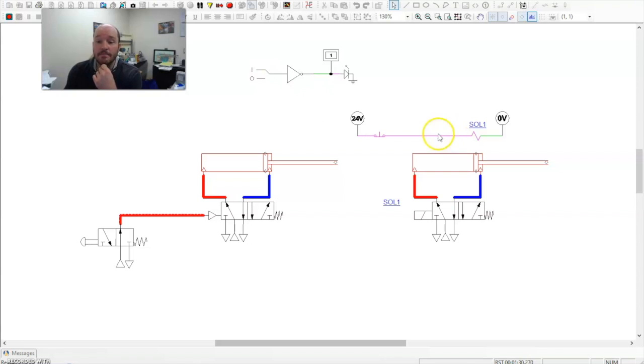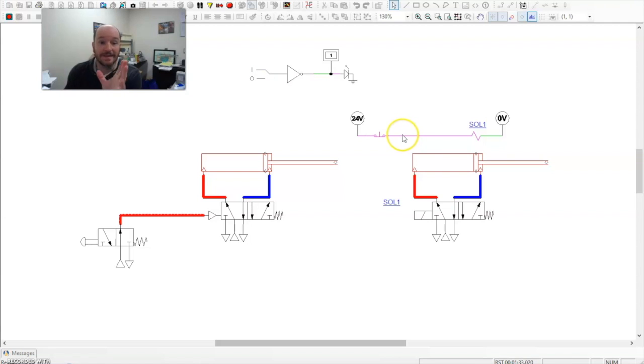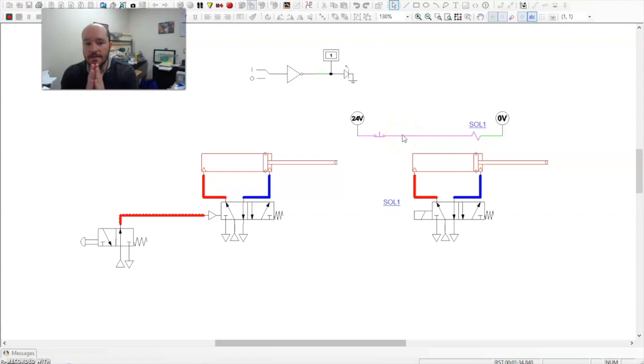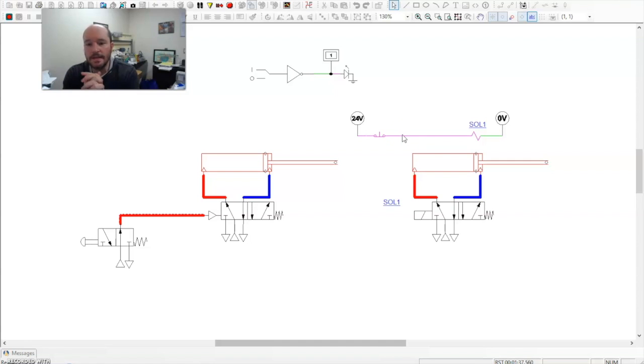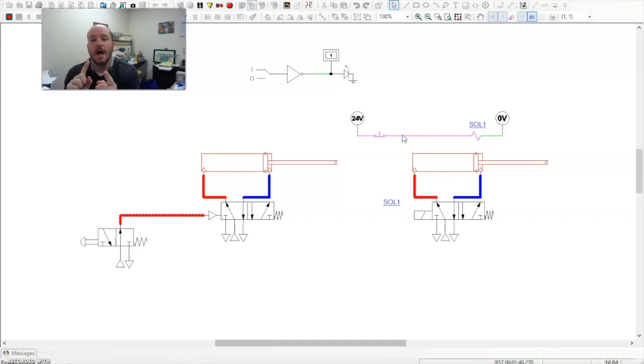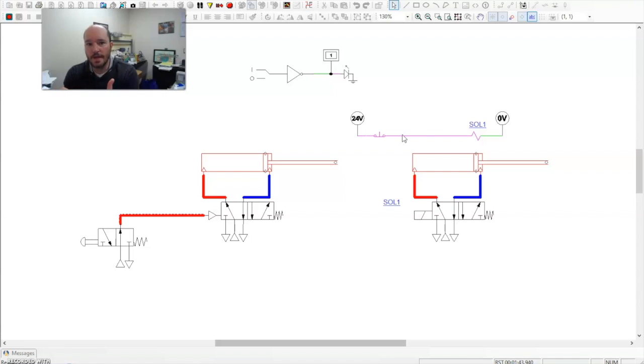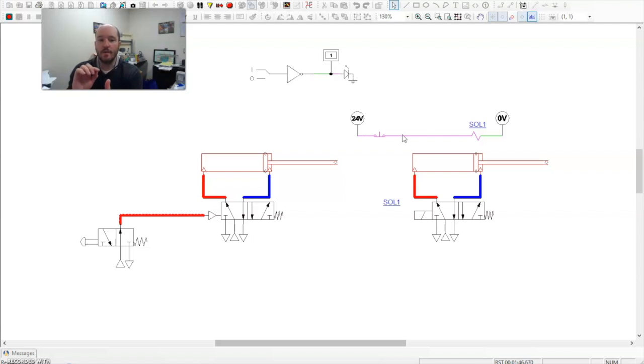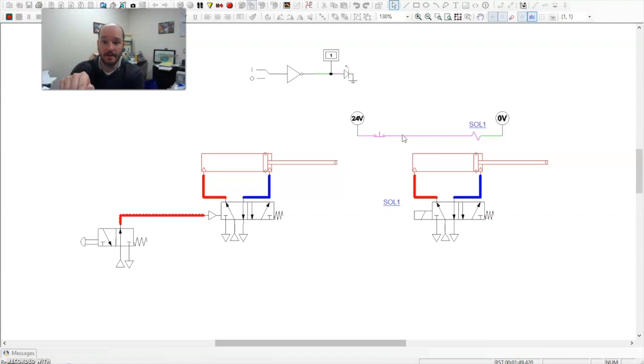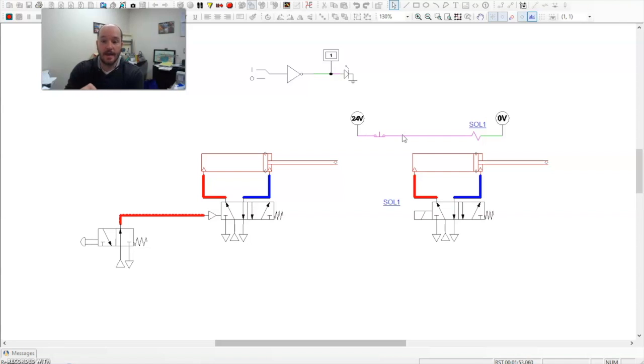Now in a motor control circuit or a ladder diagram, this can become very confusing. What we need to understand about this is we need to use a normally closed switch to make it a NOT. So if I want this on when I'm not activating the button, well, in that case, I need to have a normally closed switch.